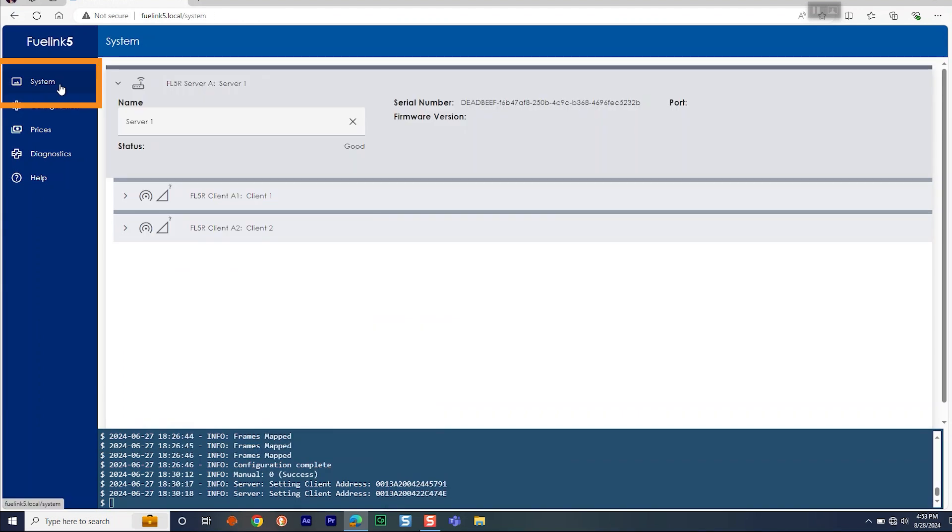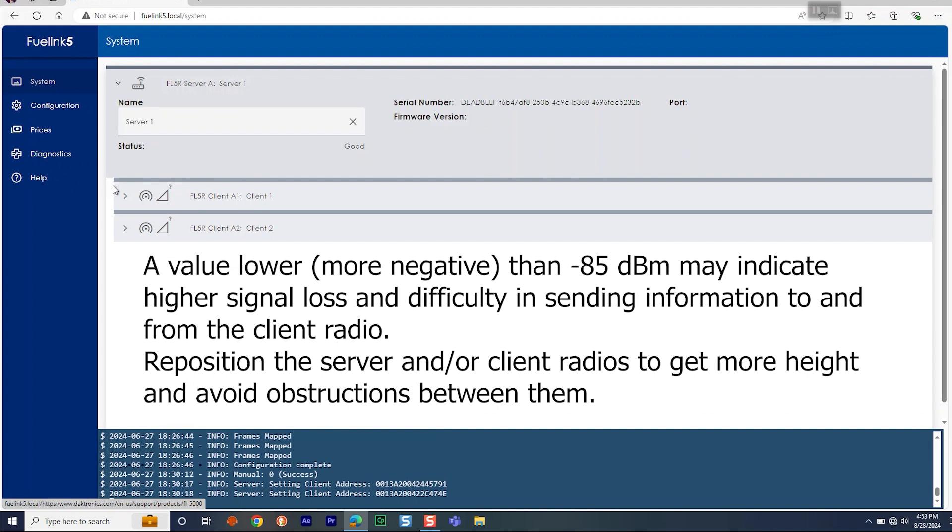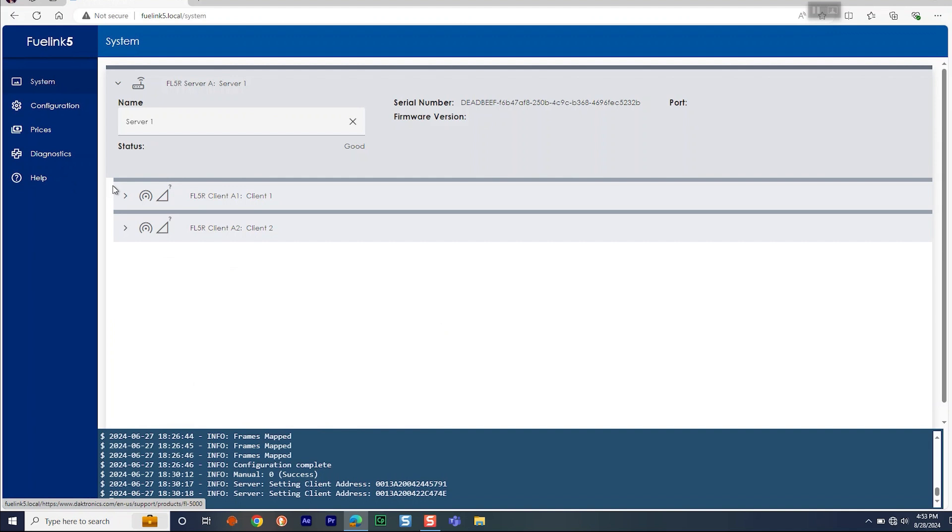Go to the System menu to view the radio's signal strength. A value lower than minus 85 may indicate higher signal loss and difficulty in sending information to and from the client radio. If this is the case, reposition the server and/or client radios to get more height and avoid obstructions between them. Once the signal strength is acceptable, you can then permanently mount the radio.